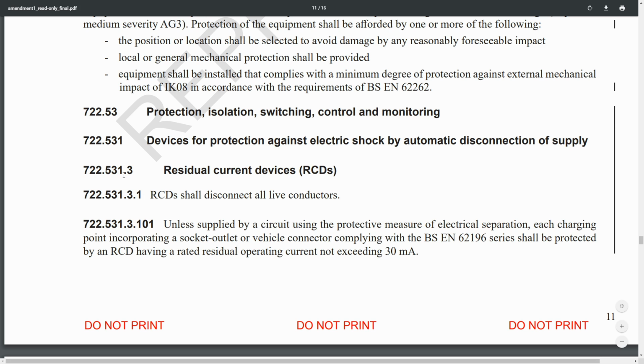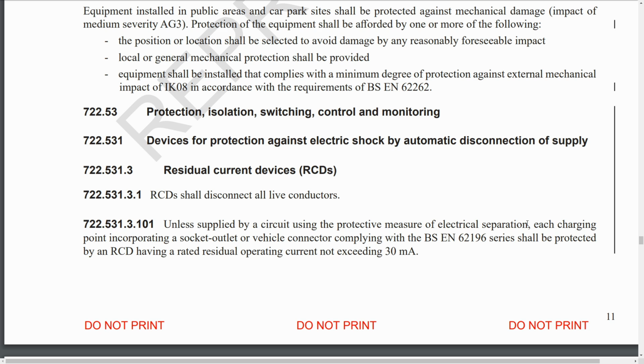It used to be 722.531.2, that has all gone, and now it's 722.531.3. So we've got RCD shall disconnect all live conductors, so that's line and neutral. Of course live covers line and neutral now, and has done for quite some time. And then we've got unless supplied by a circuit using a protective measure electrical separation, which in other words is that big isolating transformer that needs a crane to hoist it into the building.